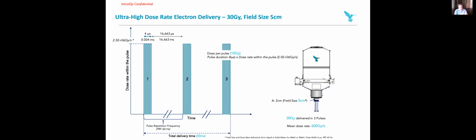So here's that pulse structure I was talking about. This is an example here: 30 gray going to be delivered in our machine. We've taken films with this, shot films with this right here. The pulse is set to 4 microseconds wide, and there's a 16,663 microsecond space and time after that till the next pulse comes along, and we repeat that 3 times.